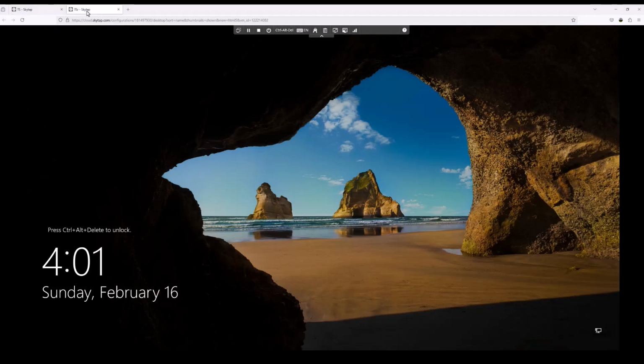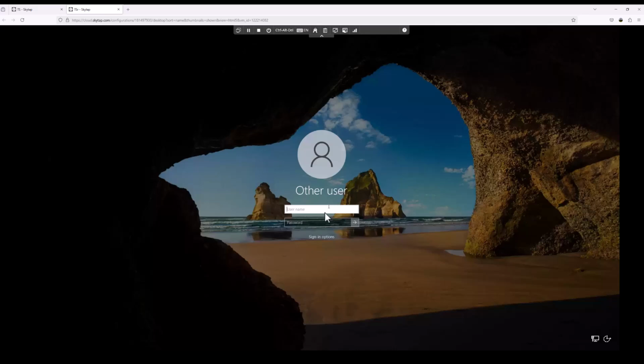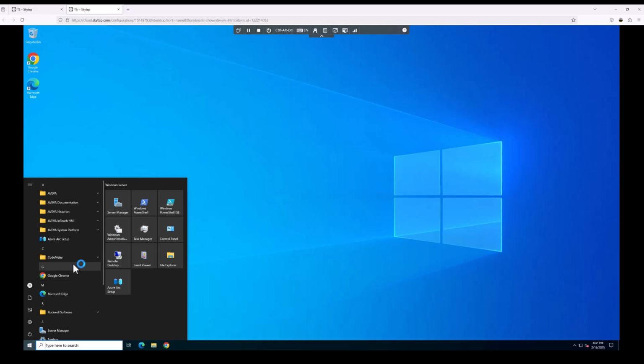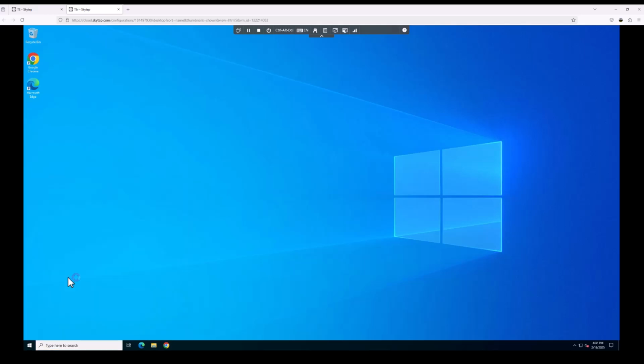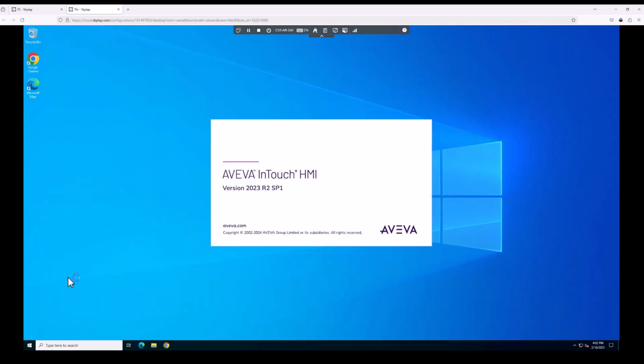Windows share folders is key to understanding how NAD works. On the source computer, in this case the terminal server, we have an InTouch setup for Mixer 100 and Mixer 200. There's two folders shared there. Now we're going to the target computer that our NAD app is going to be copied to, the runtime. So our terminal servers, where development, where Window Maker work occurs, and our TSR, or redundant terminal server, is where the runtime is going to be copied to.